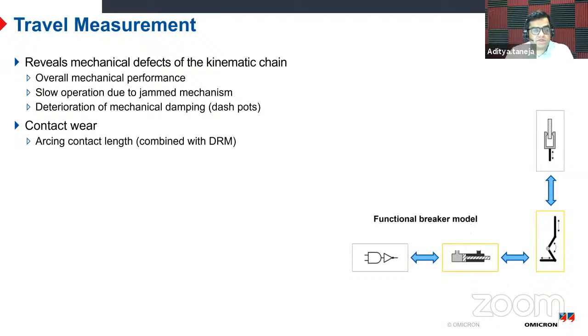The other test is the travel measurement. Again, the standard mentions this test to be done, and it reveals mechanical defects in the kinematic chain. The timing test gives us the timing of the mechanism. This gives us the distance it travels and how fast, so we can also see the speed in the arcing zone.